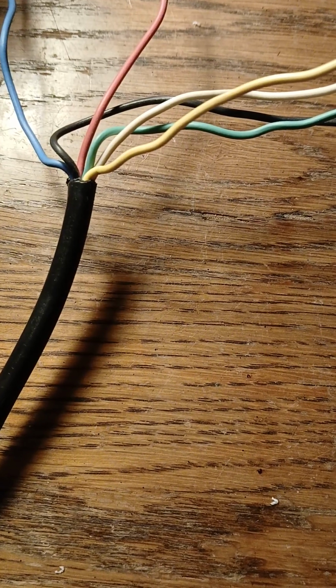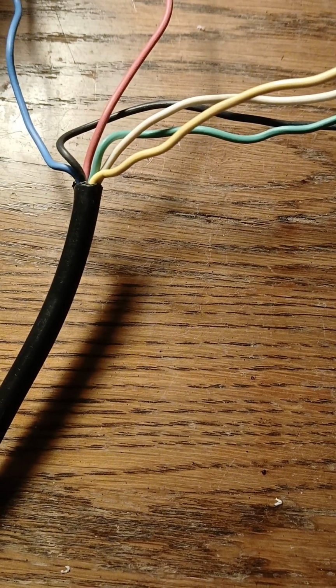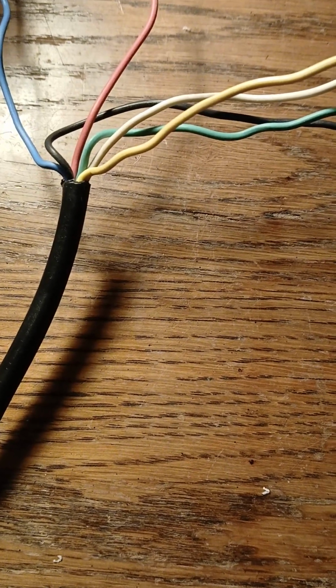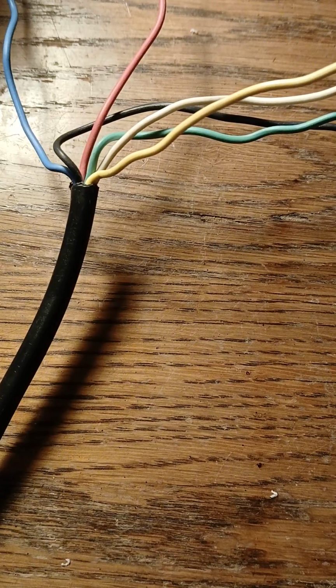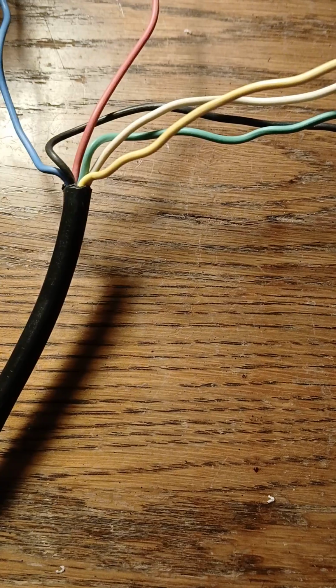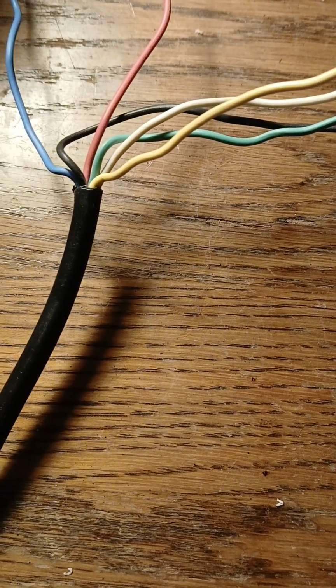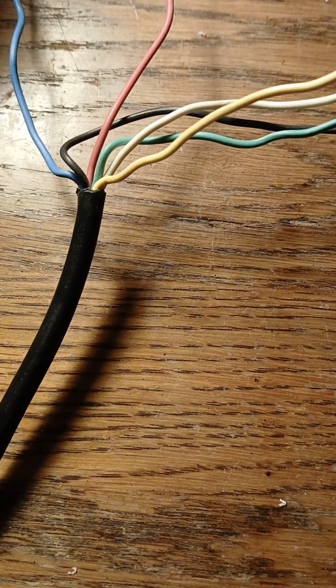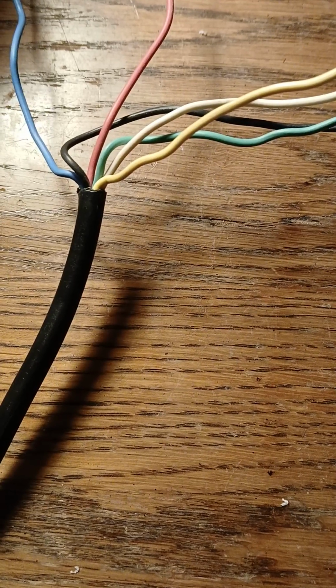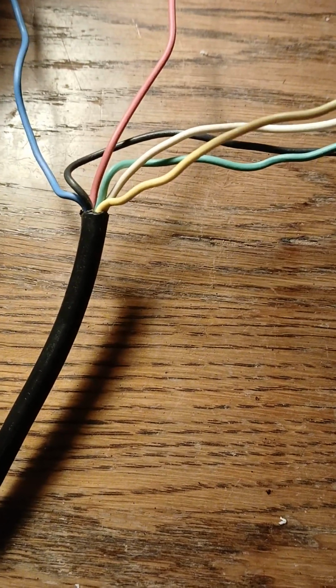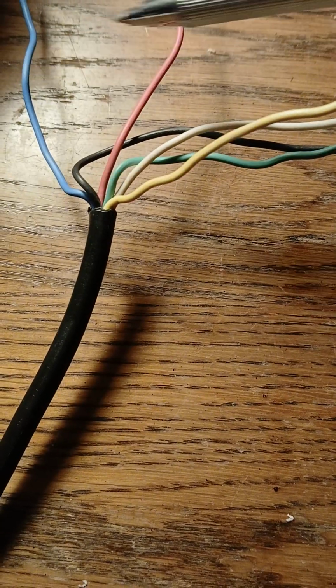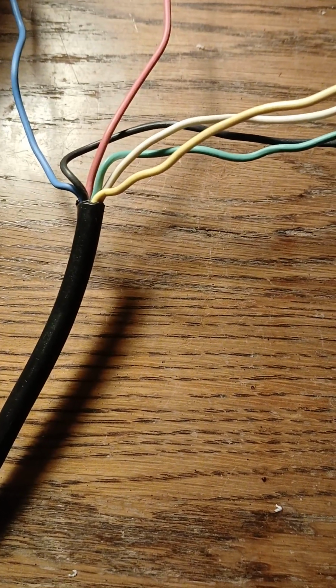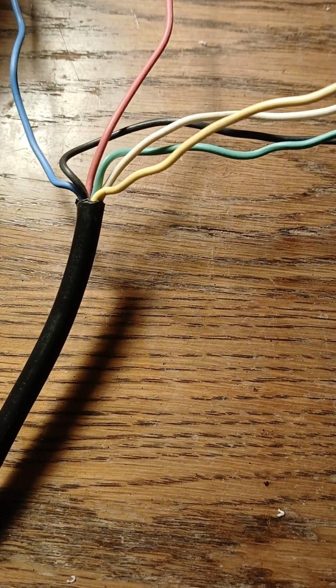Essentially, we're feeding high voltage, say 120 in a gas furnace, or 240, 208, or 230 in a heat pump situation, into the primary side of the transformer. On the secondary side, we come out with 24 volts. This is where this wire and this wire become important. This is 24 volts, the low voltage side.